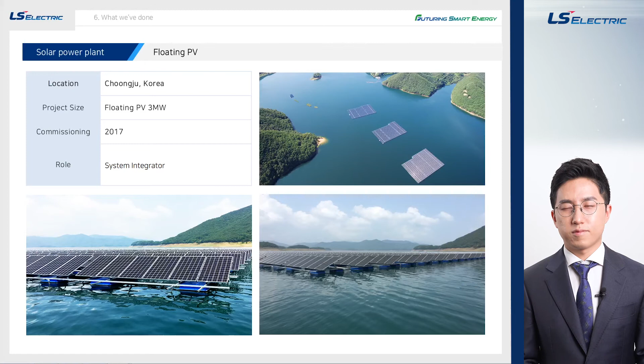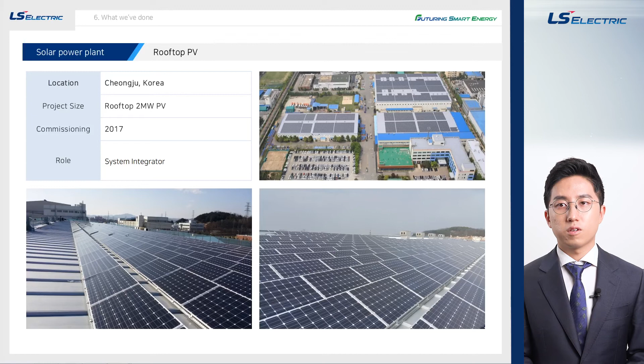This is rooftop type PV. We installed it on the rooftop of one of our factories in Korea. The capacity is 2 megawatt. It is important to connect it tightly on the rooftop. There are several ways to connect the module on the rooftop, and there should not be a hole where water could flow in. If that happens, it's a big problem because there is a lot of equipment inside the factory.